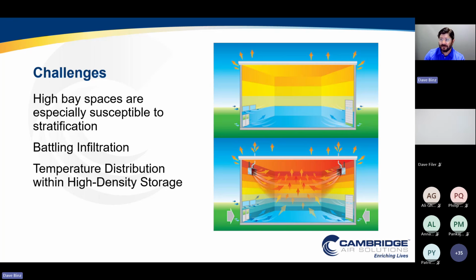And then finally, temperature distribution. As warehousing and technologies change, we're seeing much more high density racking, high density storage. So how do you get good temperature distribution inside the space? It's almost even more stringent than industrial manufacturing, where warehouses want to have as much product as possible inside. So now ductwork becomes the enemy, because any ductwork or distribution strategy that limits my ability to add racking or product becomes a challenge with warehousing business leaders.